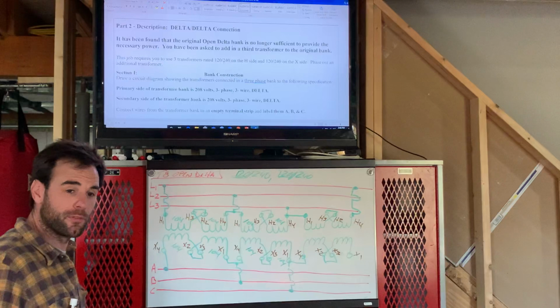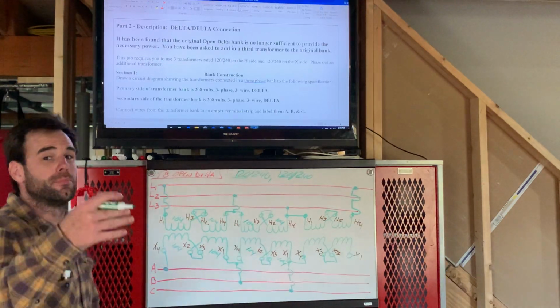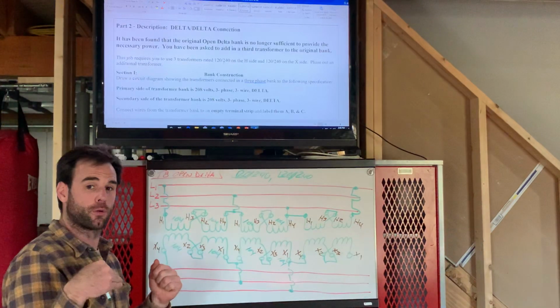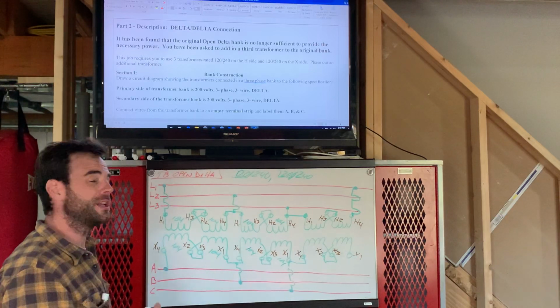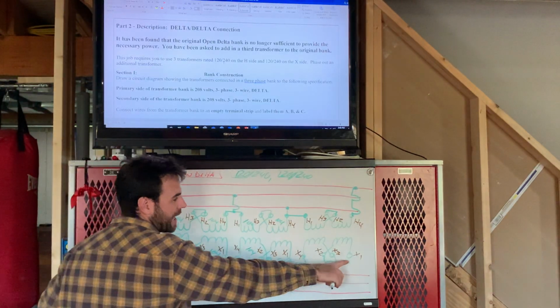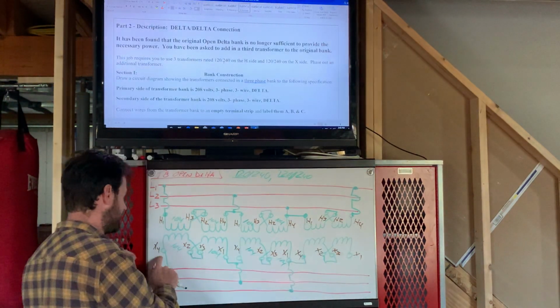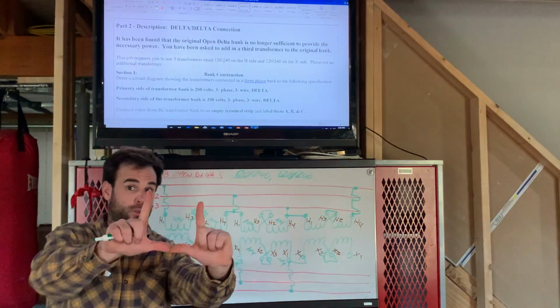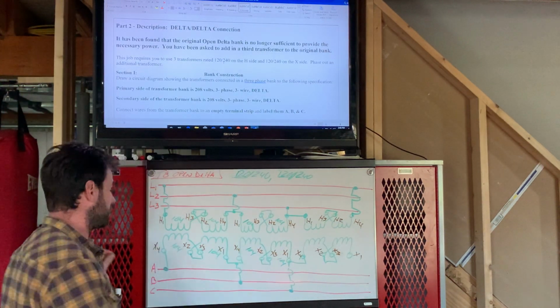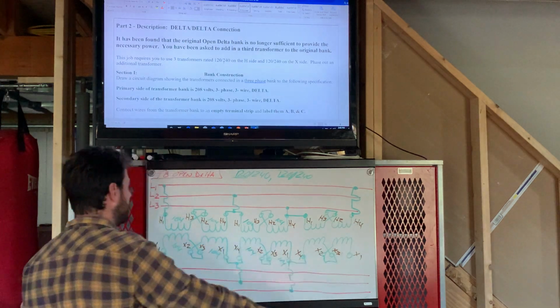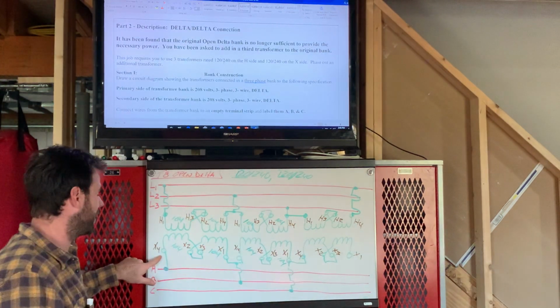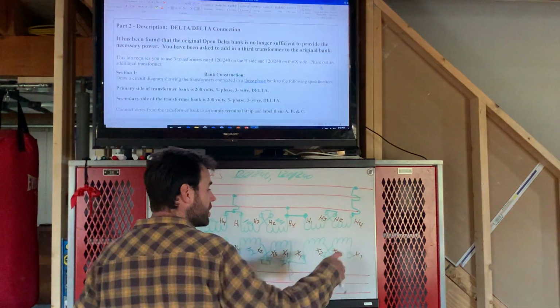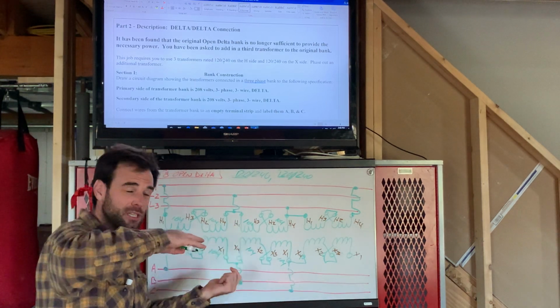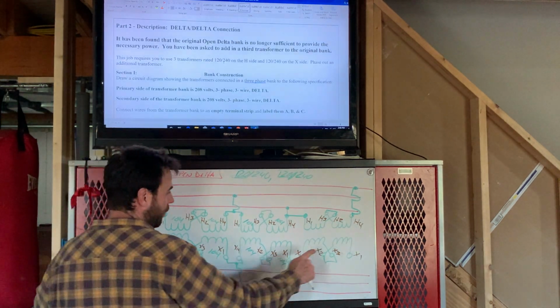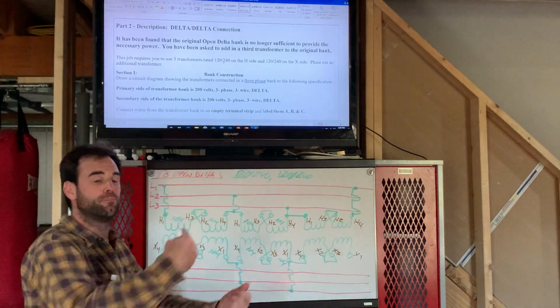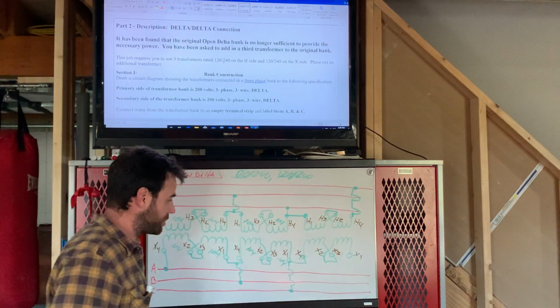before we turn power back on connected to the motor, we're going to disconnect the motor, disconnect our loads. We need to take a polarity test before we tie this X1 to this X4. We're closing the delta in now at this point, so we need to make sure that there's not going to be a difference of potential between these 2 points. Take your voltage reading. No trickery with this one like there was with the last job. Measure from X4 to X1. Anything below 5 volts, you're good to go.